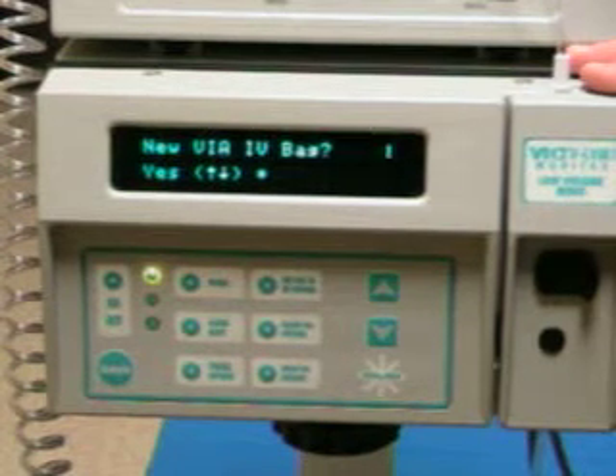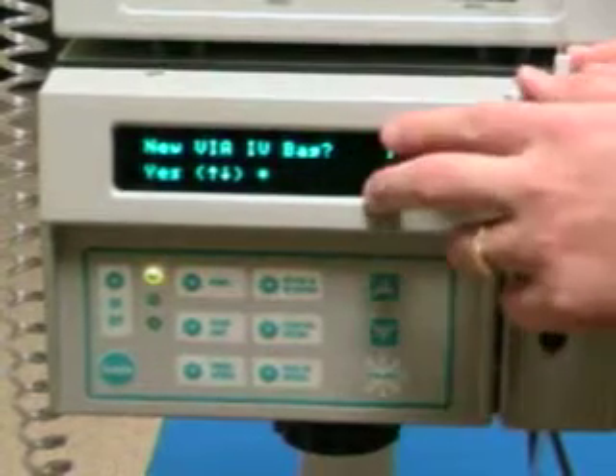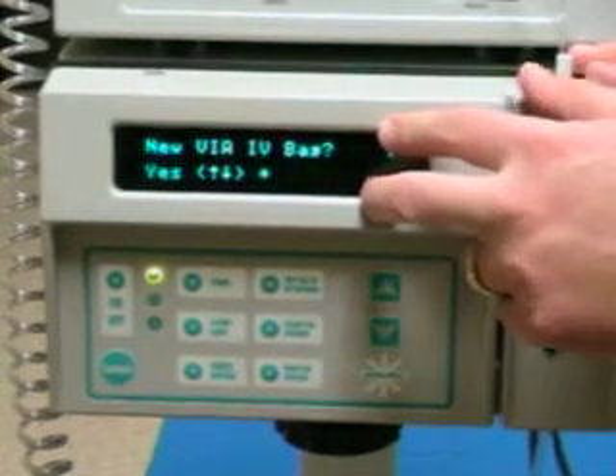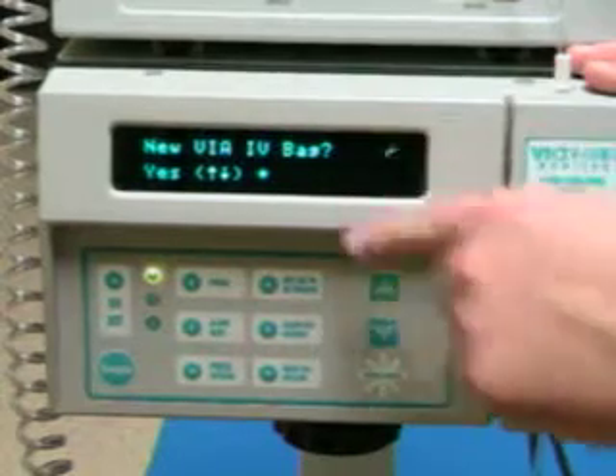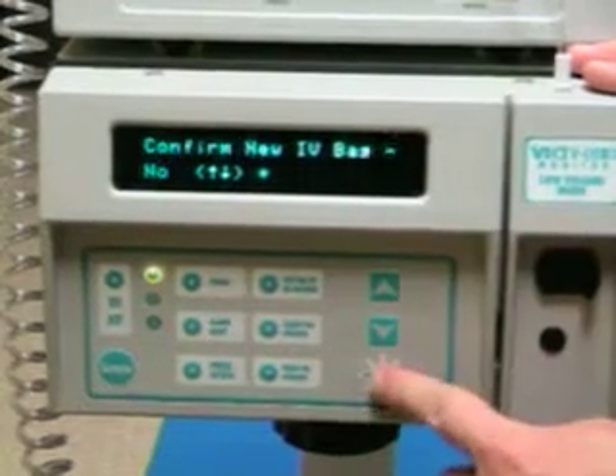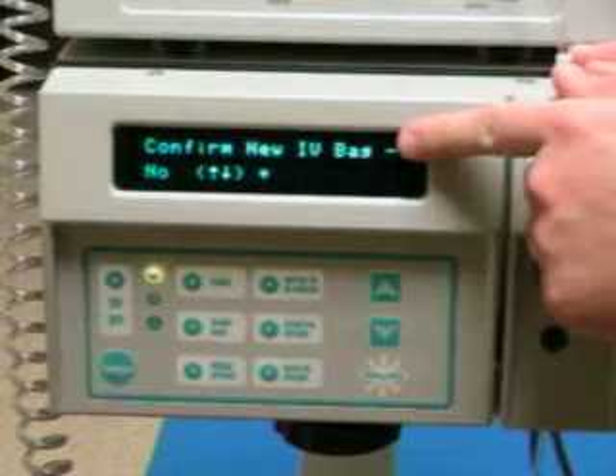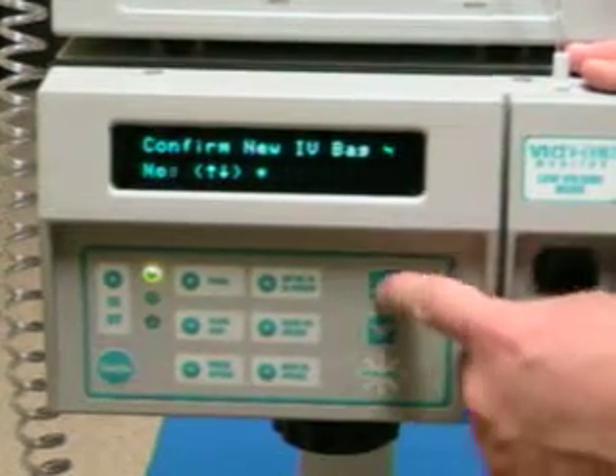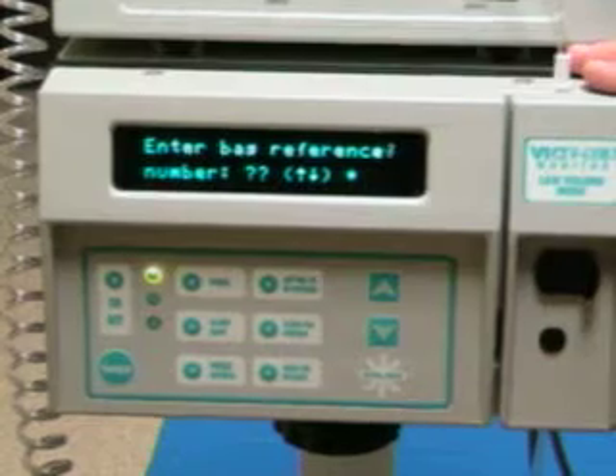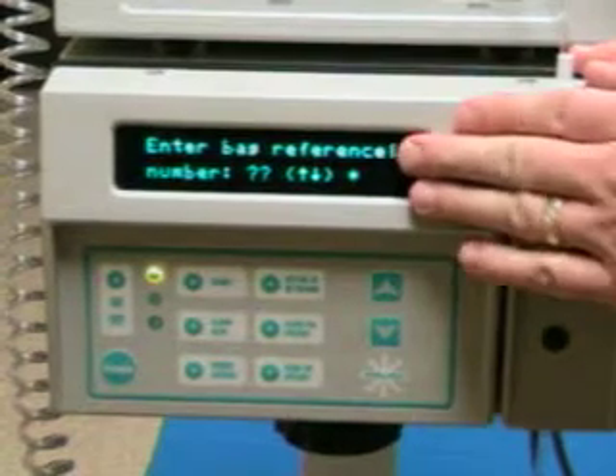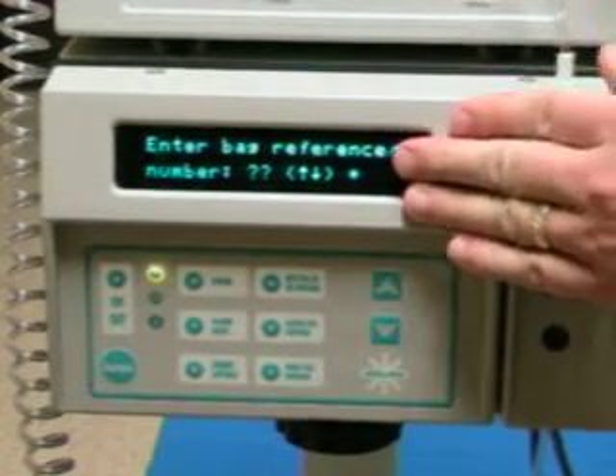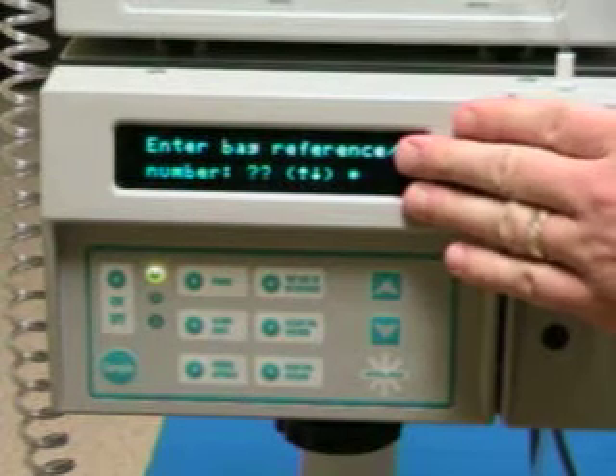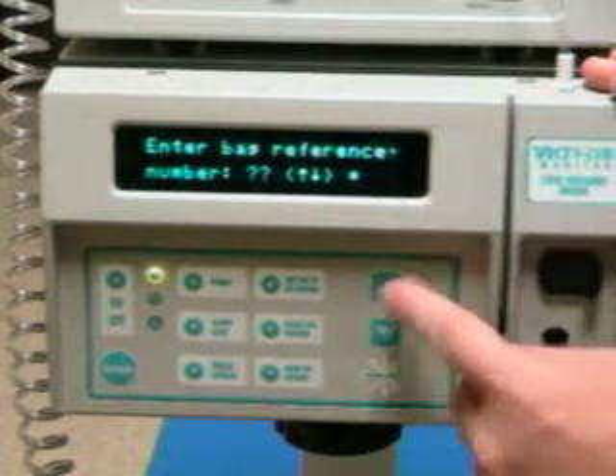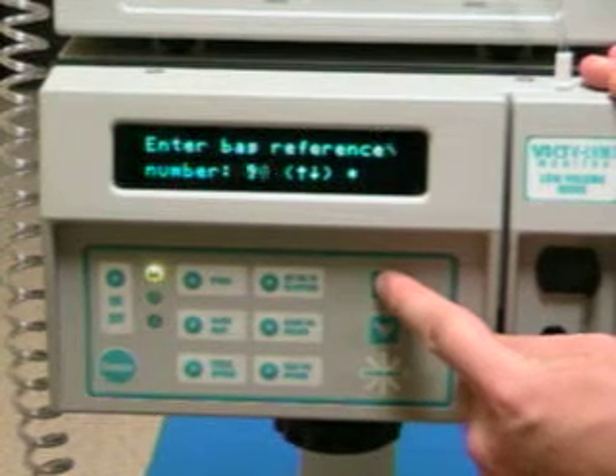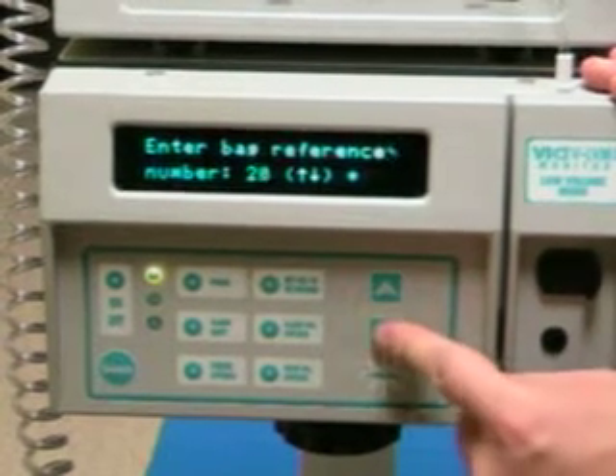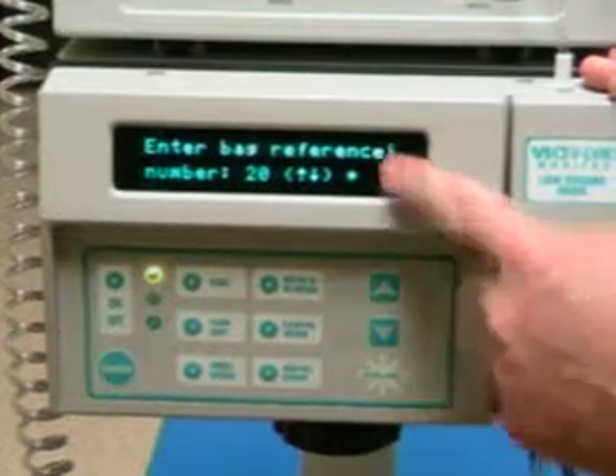So the monitor always asks you if it's a new via bag. This is also the part that you're going to see when you change bag after 24 hours. We're going to say yes, it is a new bag. We're going to confirm that it's a new IV bag by changing our answer to yes. And then this is the important part, entering this bag reference number. Remember our number was 20, and that's on the bag and the bag holder. So we're just going to scroll up till we get to 20, and then we'll hit the asterisk key.